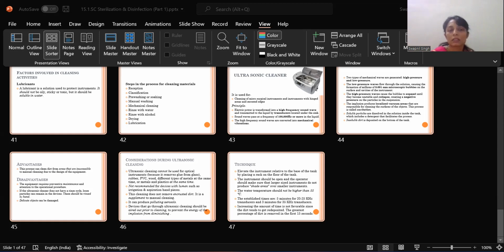Now, the time required for high-level disinfection varies according to the standards and levels fixed by the manufacturers. As per the American standards followed by the FDA, it is 10 to 12 minutes at 20 degrees Celsius, whereas in European countries it is up to 5 minutes. The concentration for use is 0.55% as per the recommendation. The solution can be reused for 15 days and has a shelf life of up to 2 years.